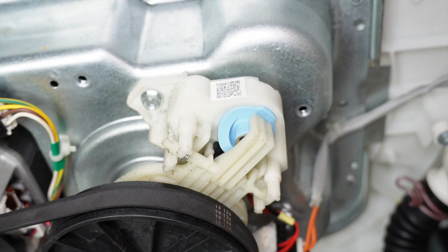Now, to remove the belt, if it is still attached, roll the belt on the 2 pulleys clockwise or counterclockwise while pulling the belt downward away from the chassis to dislodge the belt. When you have the belt off, make sure to check the grooves of the belt for oil or other debris. It's very common for oil or grease to get on the belt, which would cause it to slip, which would allow the unit not to start and run properly.